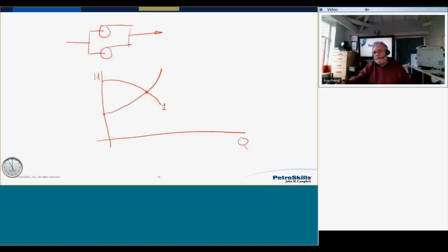All right. We now want to look at two pumps operating. So when you're operating two identical pumps in parallel, what I do is I add the flow. For this particular head, neither pump will deliver anything. Once I get down to this head, I need to add exactly the same amount of flow, which is going to be there somewhere. When I get down to here, I'm going to be about there. So we draw the curve now, which looks something like this. That's two pumps operating. The flow with one pump operating is there. So that's your flow with one pump operating. But your new pump curve for two pumps intersects your system curve there.